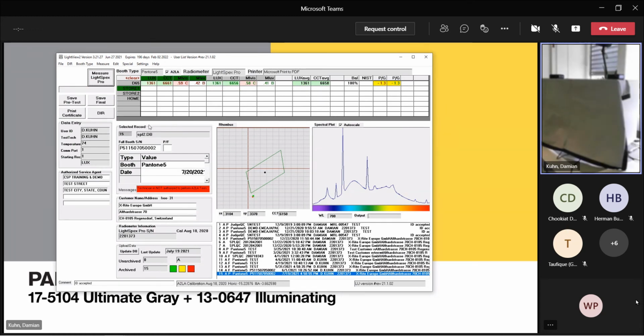Now you probably ask yourself, why are we taking 2 times 10 averaged readings? That is mainly because you can use that software for an SPL3 or an SPL2 instrument, and there it is interesting for customers, and for you, to understand the performance below the left-hand daylight lamp and filters and below the ones on the right-hand side. That's why we take 2 readings. We hit that button twice, because on an SPL device we would take the first reading on the left and then the second reading on the right for daylight.